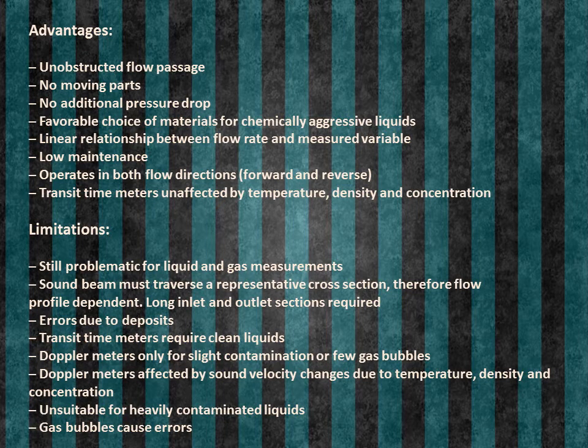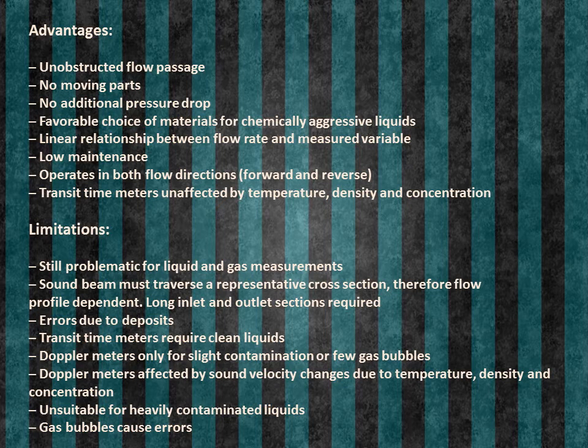Still problematic for liquid and gas measurements. The sound beam must traverse a representative cross section, therefore flow profile dependent. Long inlet and outlet sections are required. Errors due to deposits.